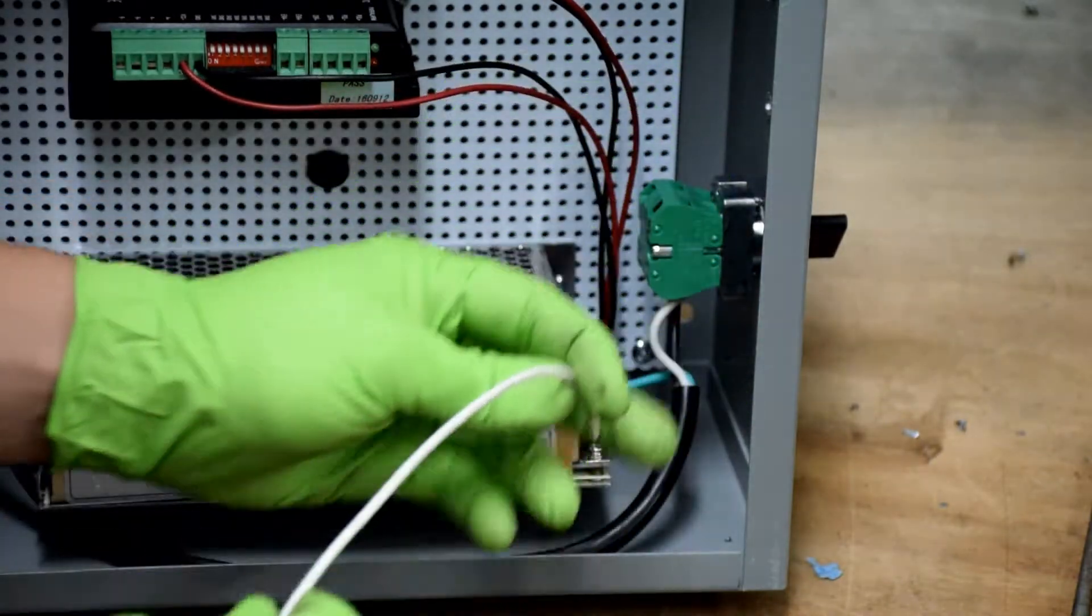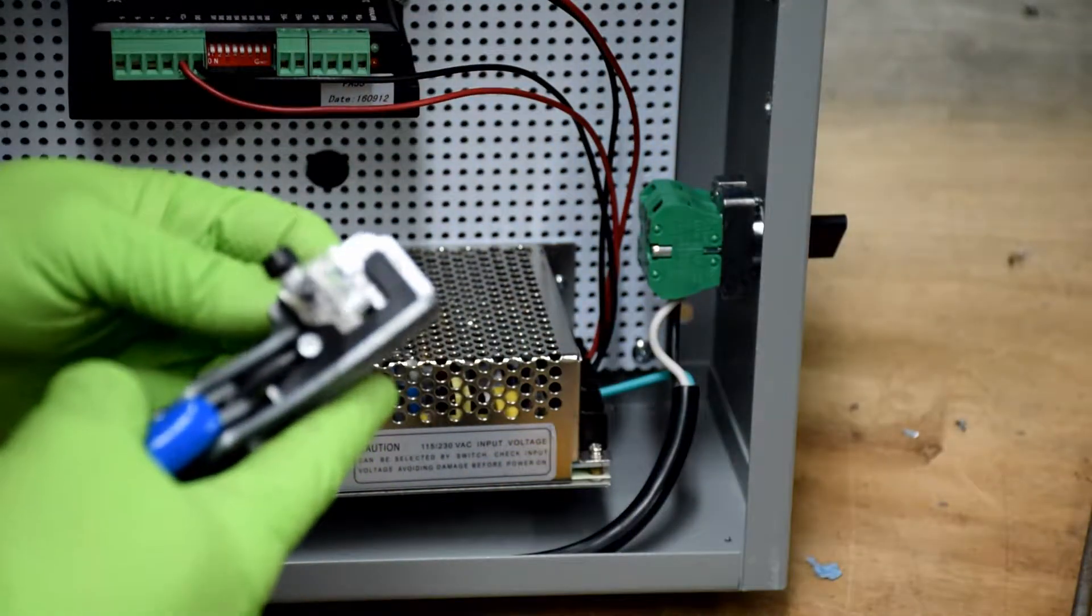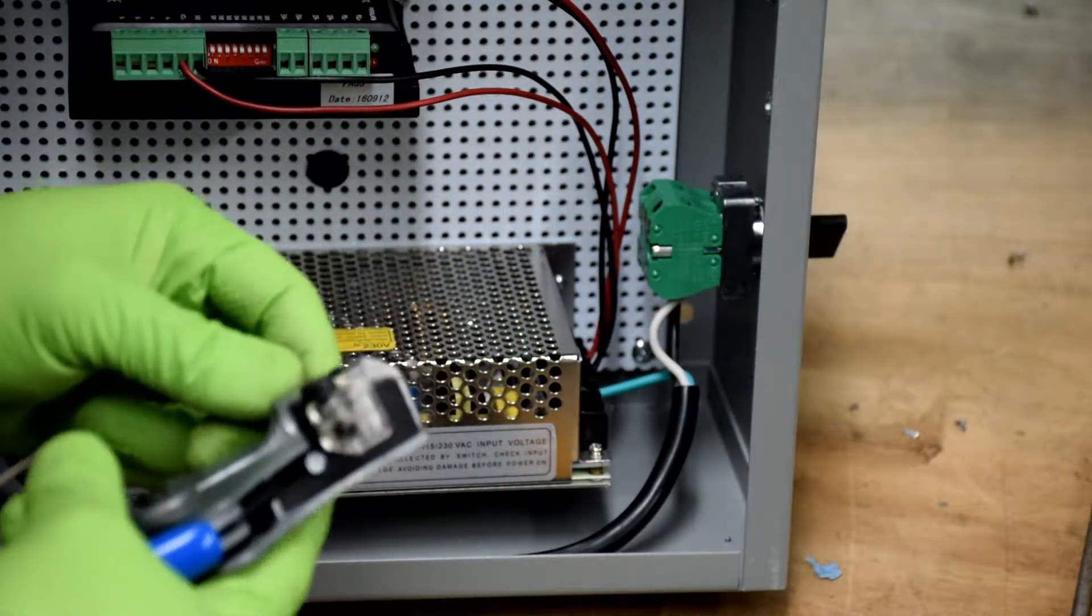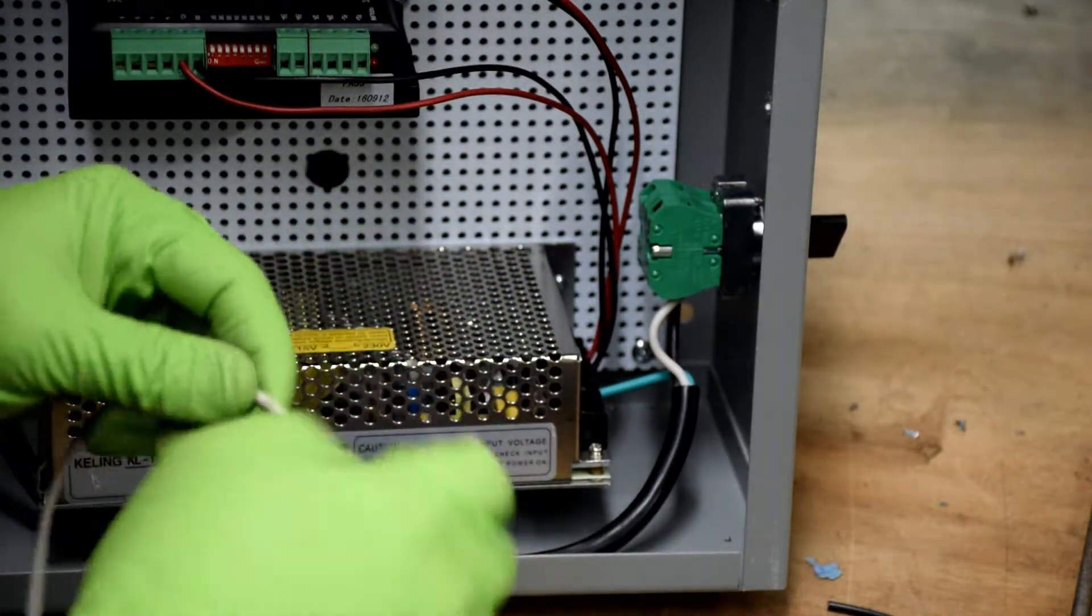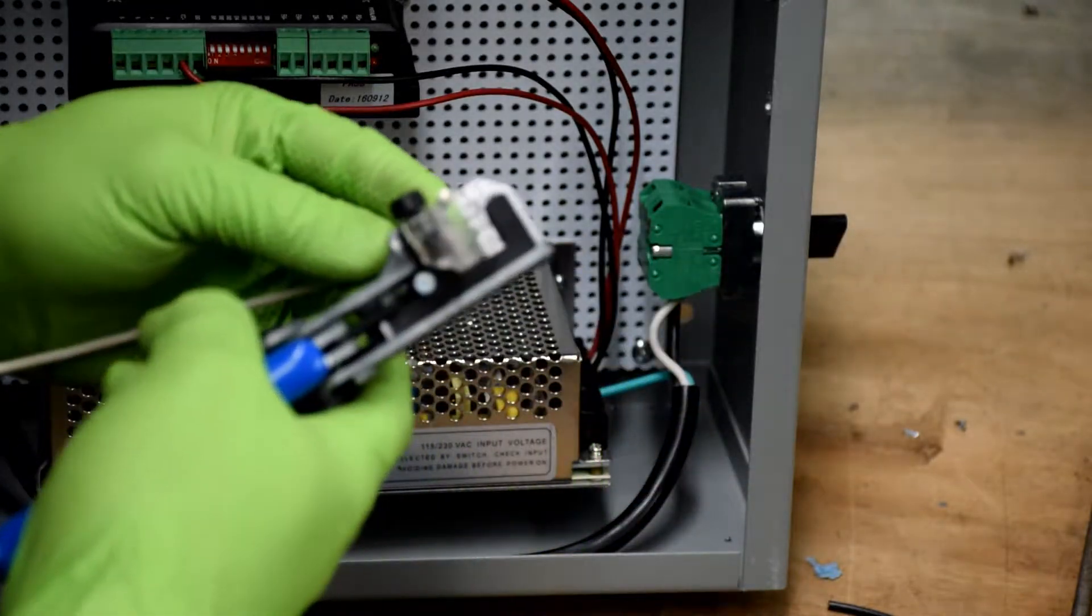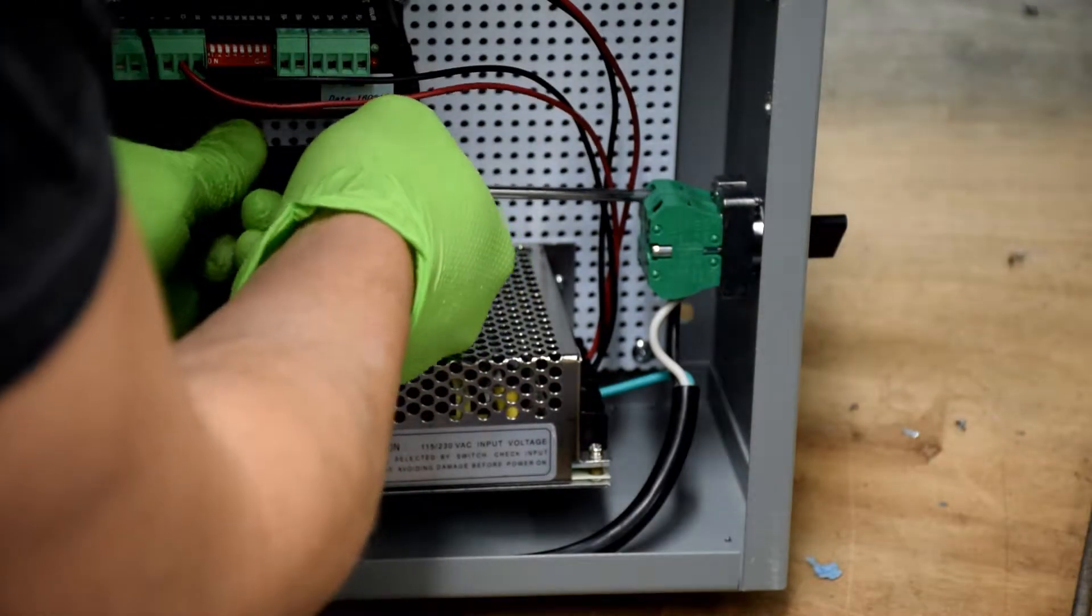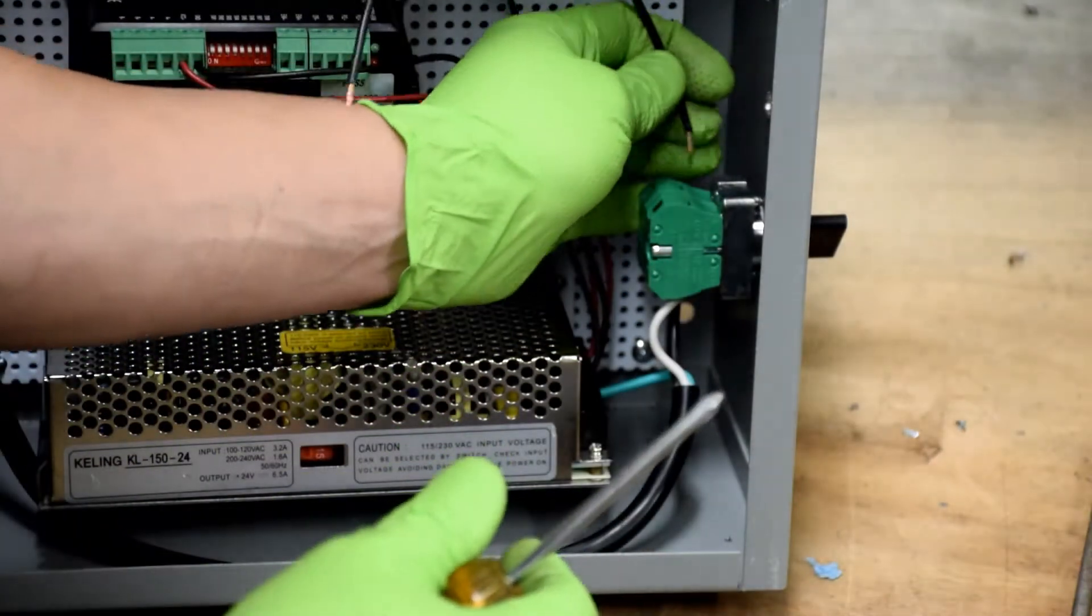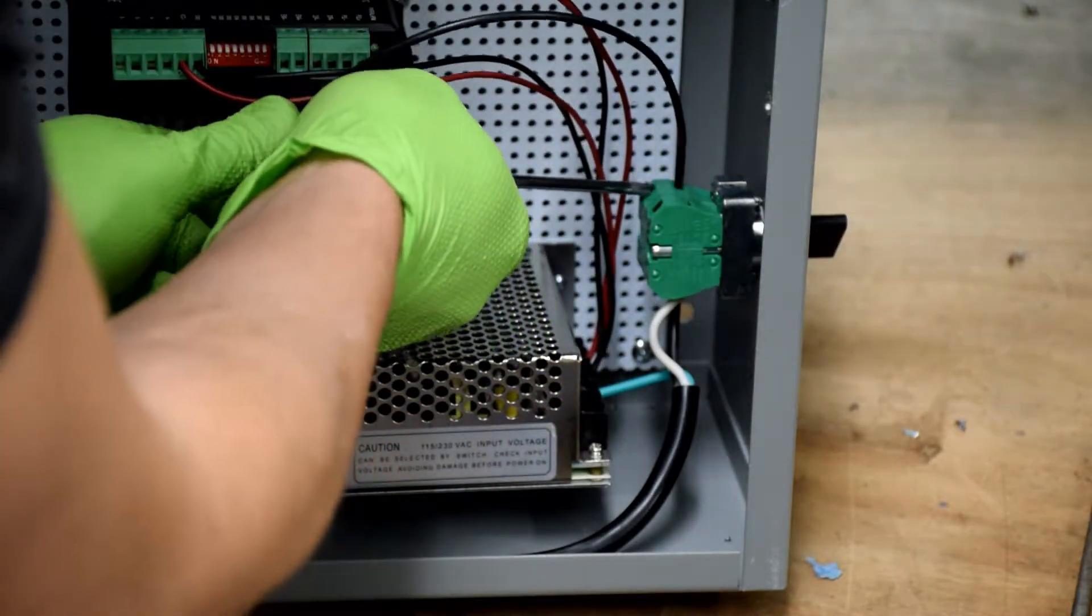And these are going to be wired into the power supply into the line and neutral terminals. And those are designated by an L and an N. So just strip off the wire, twist up the ends like you've been doing. Make sure you put the correct wire in the correct terminal, black to black and white to white.